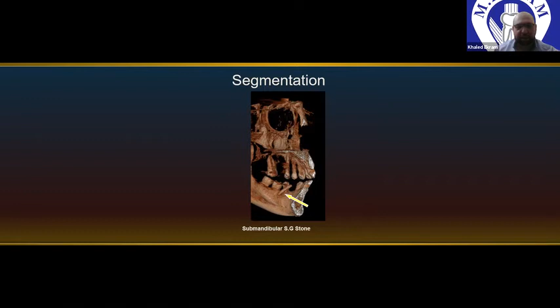The limitations of the CBCT, we have some limitations, of course. First is the higher image noise, because in this modality there is a single cone beam, or cone-shaped X-ray beam, that covers the patient's head, so it covers a larger area. So more scattered radiation can result from this maneuver. Second is the poor soft tissue detail in relation to multi-slice CT and, of course, to MRI. Third is that metal artifacts have a very big influence on the image, and this is the main enemy for CBCT, the metal artifacts.